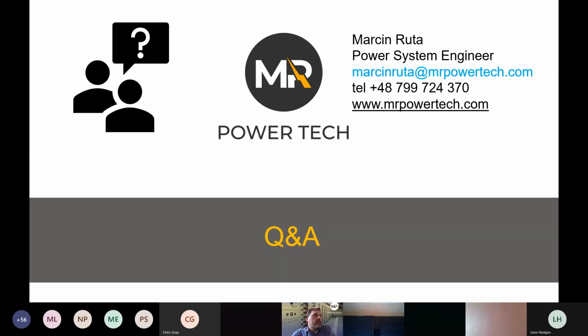Chris, for there is risk assessment involved. How do you generally recommend approaching arc flash studies for medium and low voltage switchgear control that has undergone the classification? In theory, the operators are protected around this equipment with all those covers in place. Would you only recommend an arc flash study when accessing the equipment for modification or maintenance when the equipment is live? So once we do the study, we know the result. It doesn't matter if your doors are open or closed.